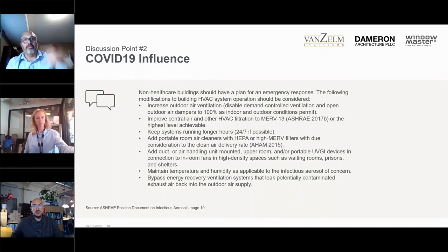So there is a potential for cross-contamination. If you're dealing with a 100% outside air ventilation system, what they're recommending is that during this time, we may want to disable that energy recovery wheel, so if any particles are coming back to get captured, they're not being transferred to the supply and then blown back in.